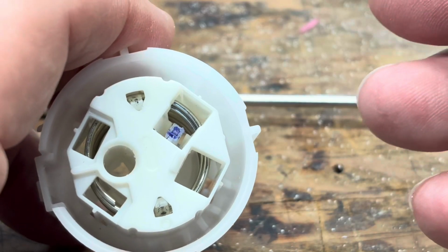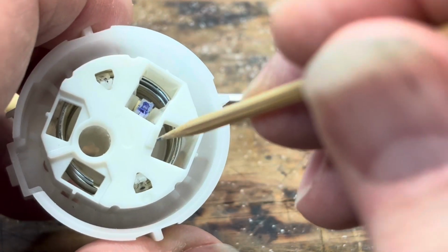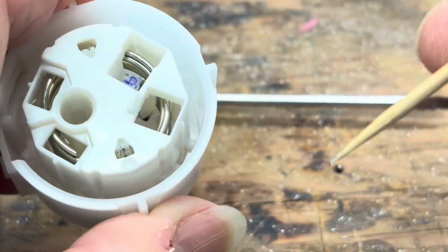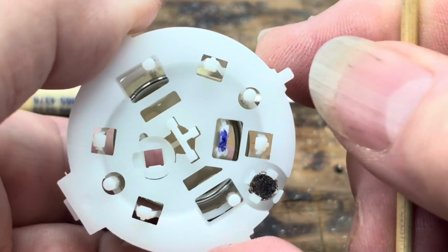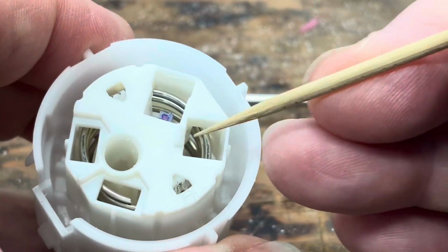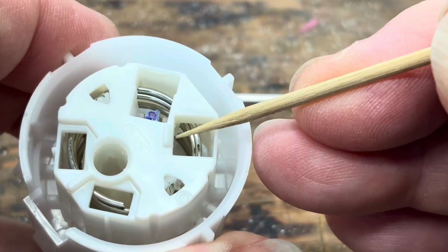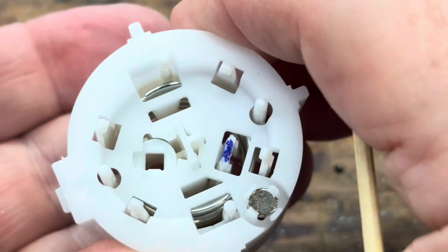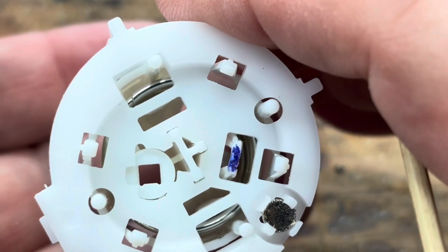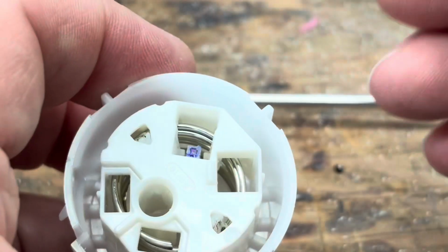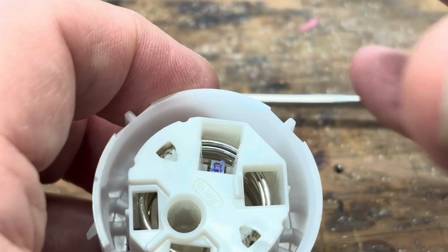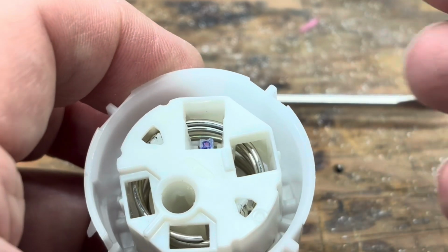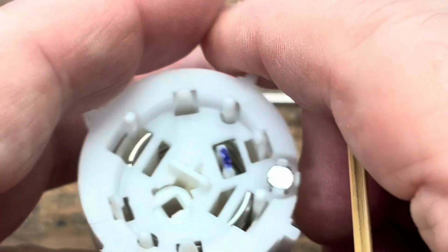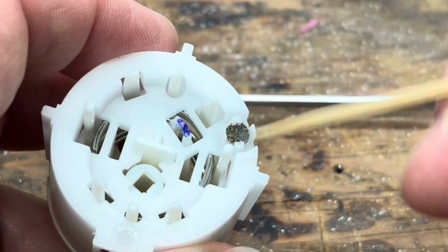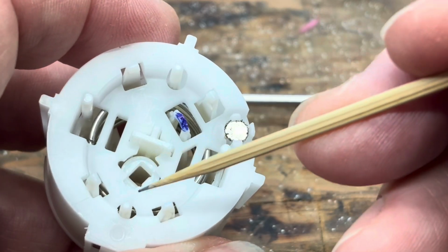What triggers it is that hook in cup 2 fits through this hole, and as this device travels towards the patient's arm, that hook suddenly hits this shelf, arrests the travel of cup 4. 3 continues to travel. Those pinch points are released. The spring can then extend beyond those shoulders and push cup 4 away from cup 3, which releases the fingers that are holding the device and retracts the needle.